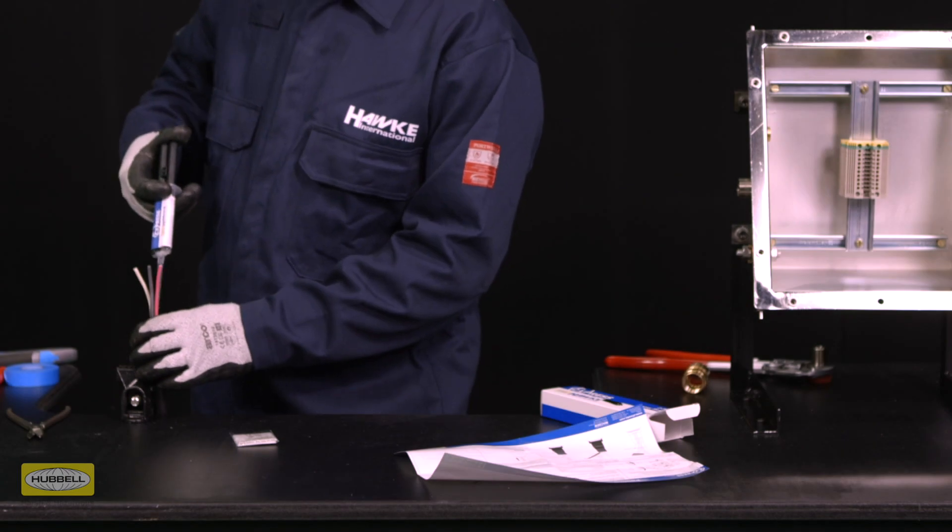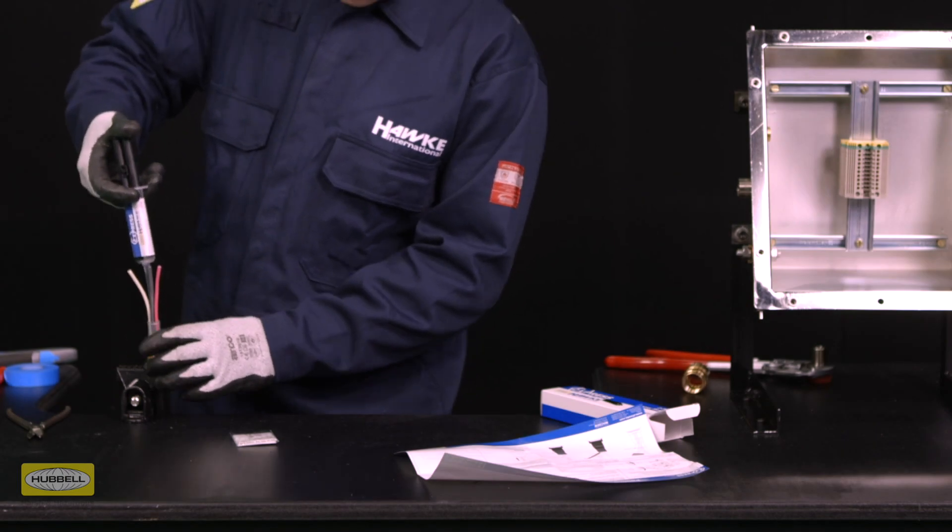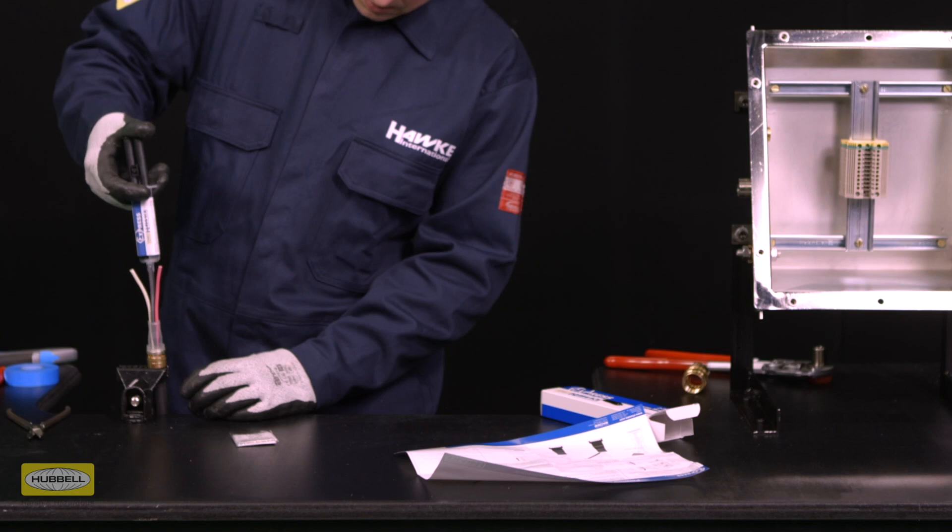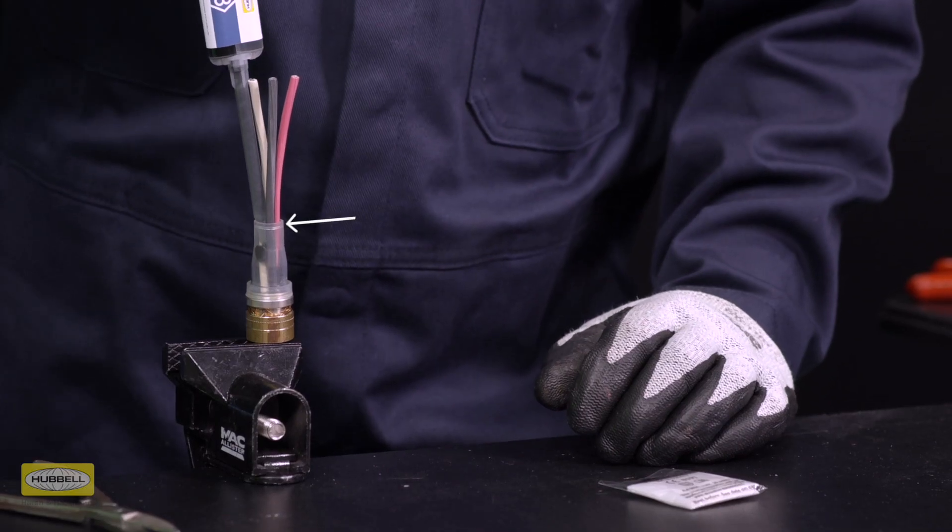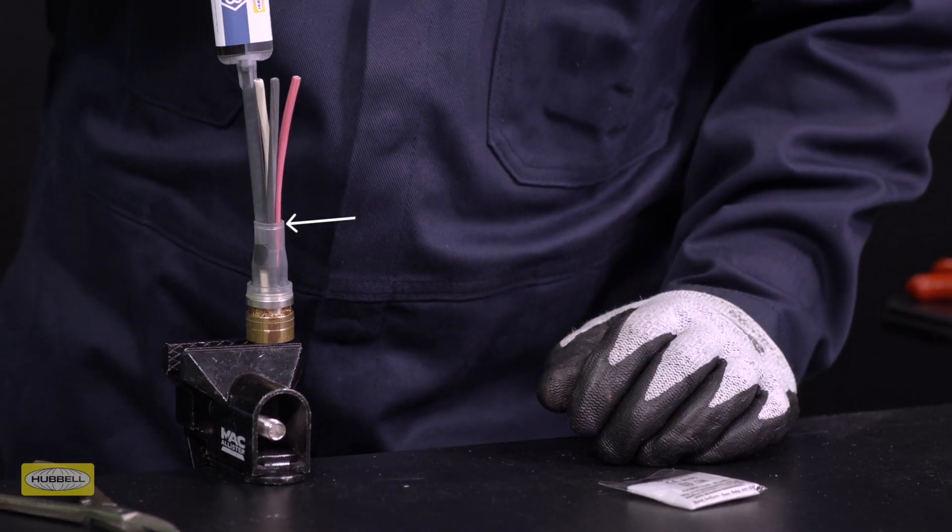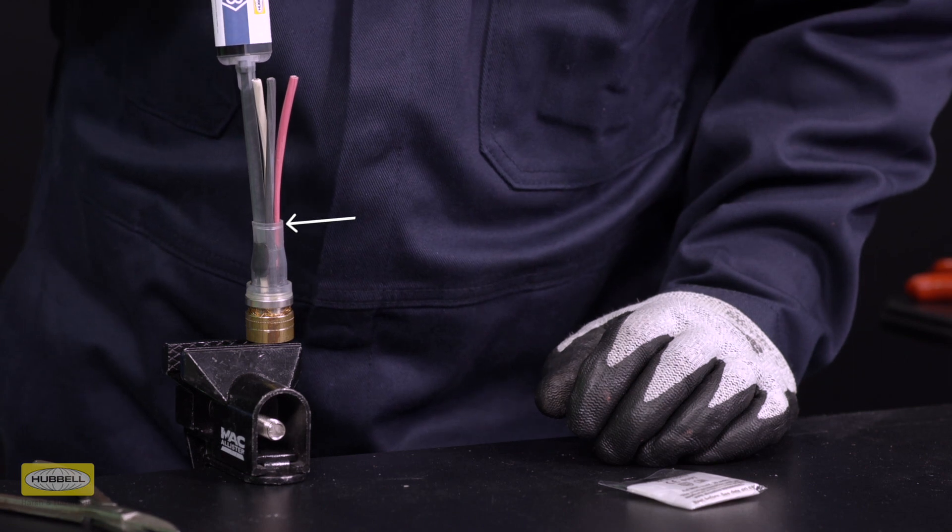Ensure the gland is held vertically. With the nozzle starting as far down the pot as possible, fill the resin to approximately three millimeters under flush. This is indicated on the silicone pot by the fill line shown on screen.